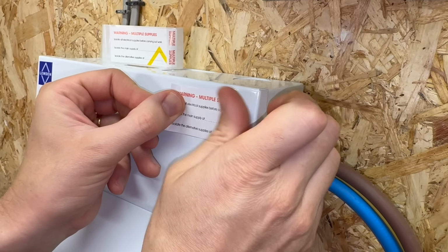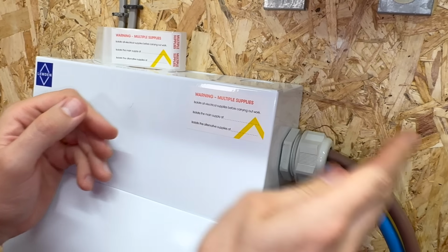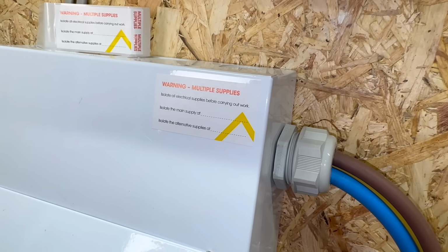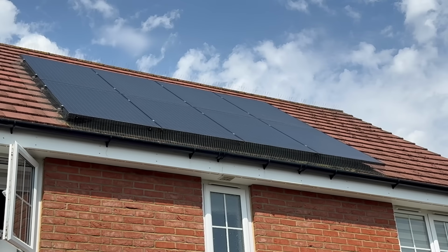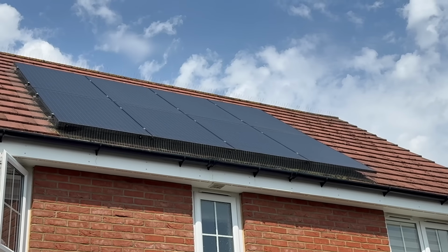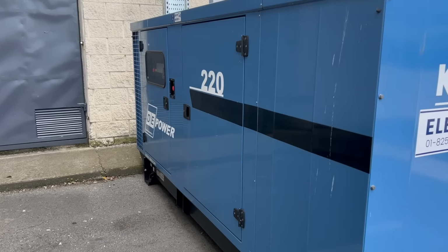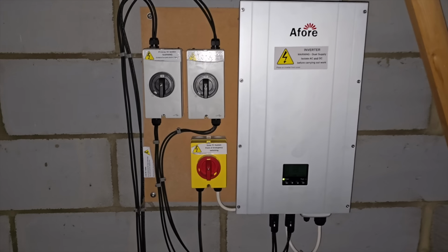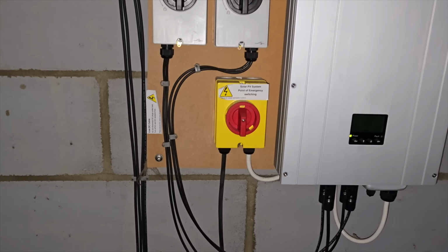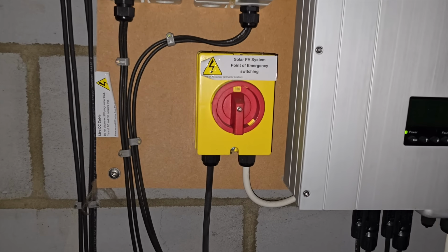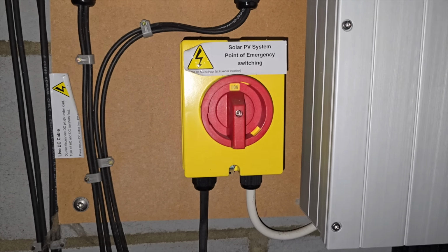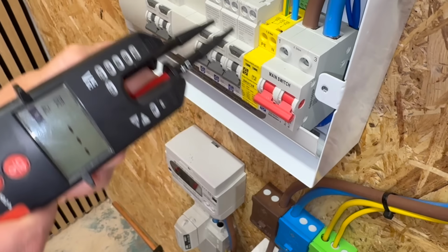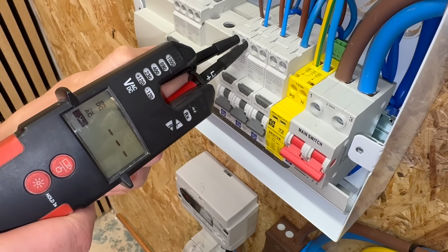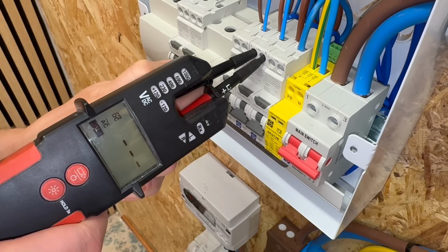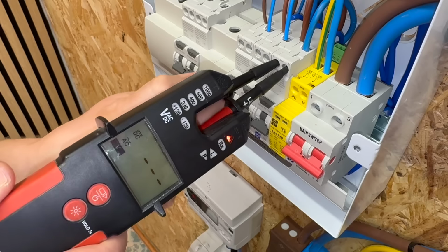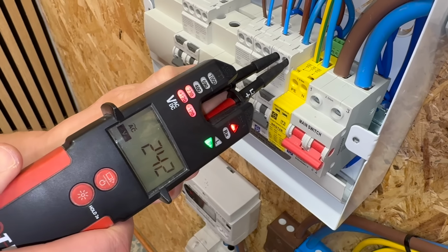What though if they were slightly less than diligent? Well, the first thing to do is to make sure you've had a good scout around the property looking for other sources of supply. Photovoltaics are hard to miss, but there may be other things like backup generators on some installs. There should be isolators on or near power generating equipment to disconnect the outgoing supply from them, so operate these and lock them off with signage as usual. Then, as part of your safe isolation process, make sure you've tested the seemingly outgoing conductors on the circuits within the consumer unit you're isolating. Following these steps should help to keep you safe.